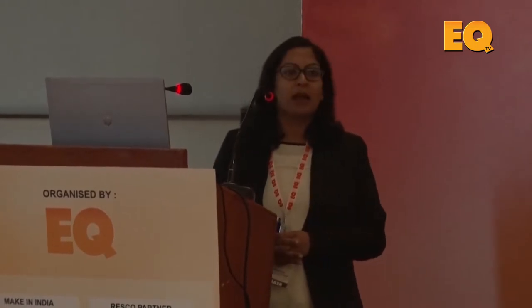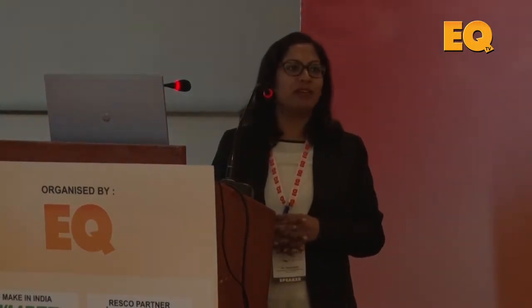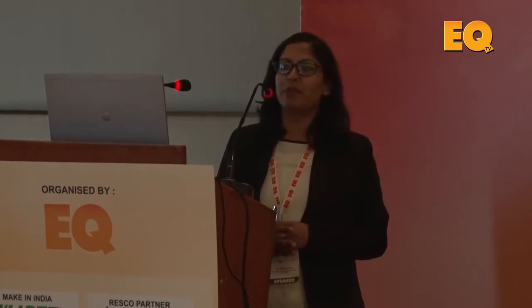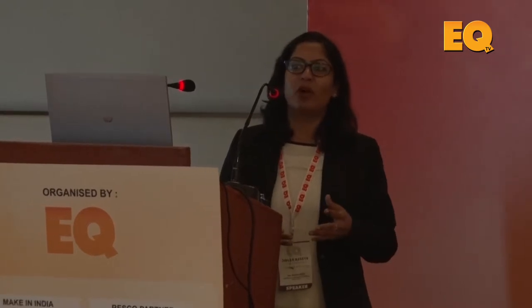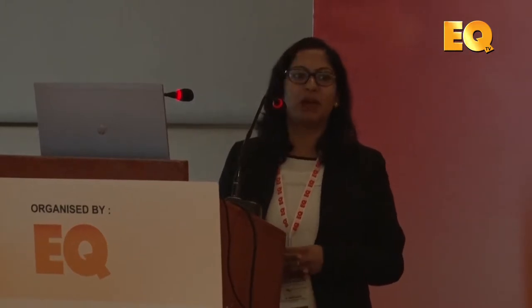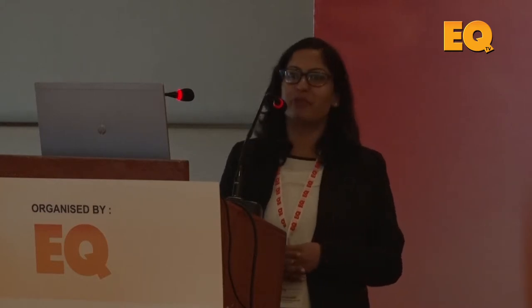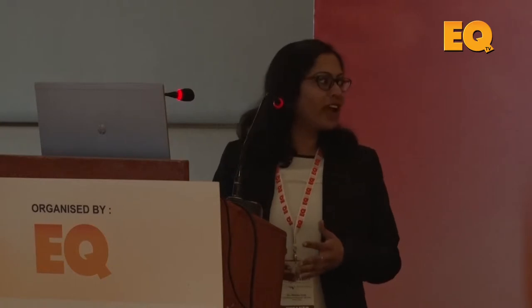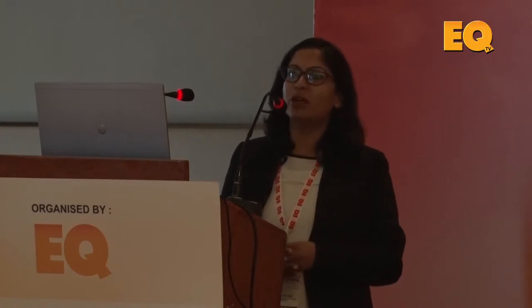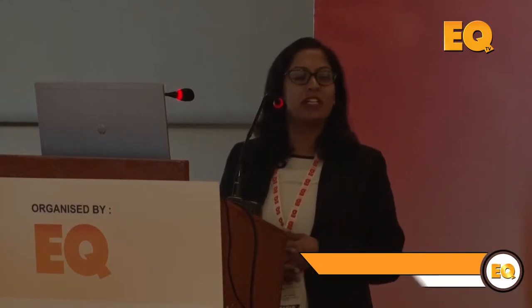Before I start: has anyone thought how much money a developer could lose if the PR number changes by 1%? For example, if the guaranteed PR is 78% but what you actually get in the plant is 77% — how much money on a yearly basis would a developer lose, even at a tariff as low as 2.5 rupees? I did some math: even at 2.5 rupees tariff, it means a loss of about 80 to 85 lakhs a year for a 100 megawatt plant.